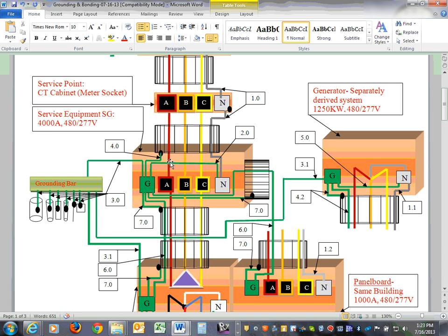4.0 is very important. Now you came from the bottom of the switchgear. You can see with 4,000 amp and 3200 amp switchgears, right? Switchgears are open bottom. So when you bring your rigid conduits, if you're using rigid, if you're using PVC, number 4 does not exist. Number 4 is only bonding the conduits bringing the power into the switchgear at the service.